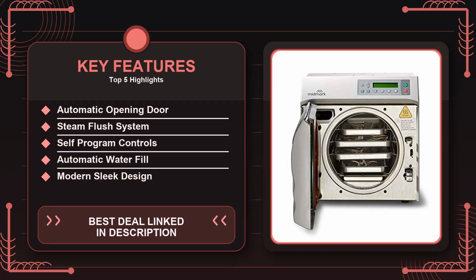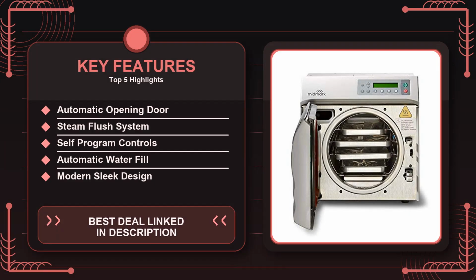The second feature that gets a lot of buzz is the steam flush pressure pulse air removal system. This is the mechanism that's supposed to drive out trapped air bubbles before the sterilization phase, ensuring that steam reaches every surface. For people who have tried lower-priced steam boxes, air pockets are a common source of failure. Those spots never reach the 121C needed for true sterilization. In the M9, the pressure pulse does a decent job. The LCD display shows an air removal phase, and after a full cycle the internal temperature consistently hits the target range. However, the system does add a few extra minutes to the overall cycle time, so you're looking at about 45 minutes for a standard load instead of the 30-minute cycles you might see on some competing units. If you're on a tight schedule, that added time could feel like a hidden cost.